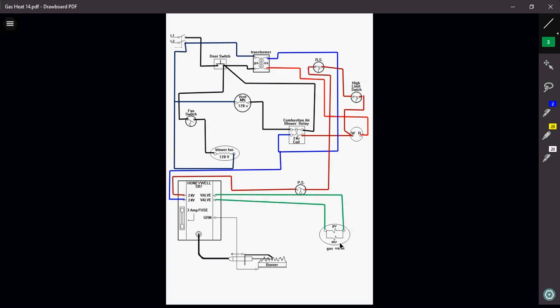Okay? So once my safeties have all proven that everything is good to go, my ignition module will now send the signal to my gas valve to open, which will now ignite my burners. And once my burners ignite, my little flame rod or my flame sensor is going to pick up a microamp signal, and that microamp signal will be sent back to the module, telling the module that you had a successful light off of the gas. The furnace will continue to run until it reaches about 140, maybe 150 degrees, depending on the manufacturer. And once that happens, my fan switch is going to close, bringing on my blower motor, which will now deliver that warm air into the space so that I can now deliver the heat.